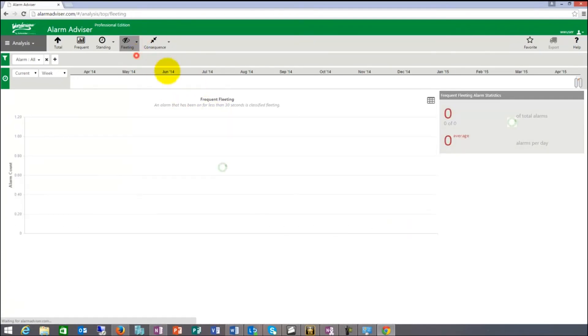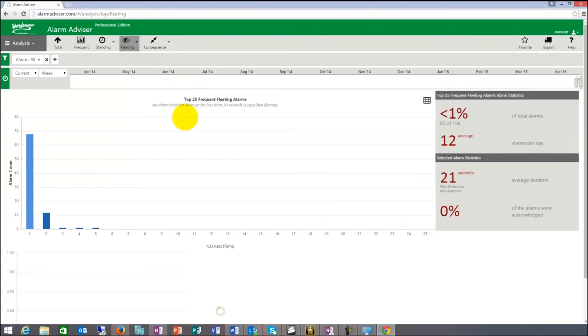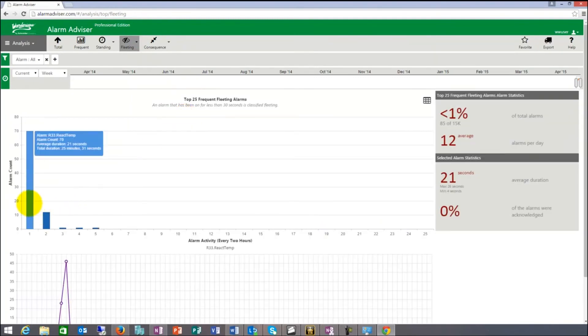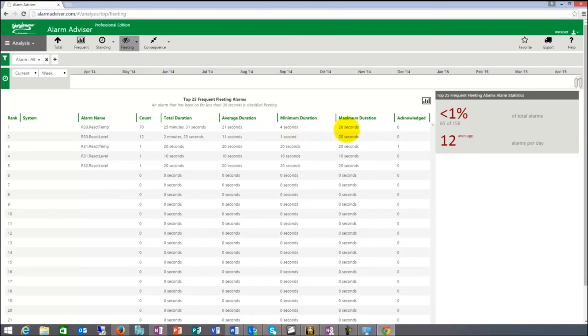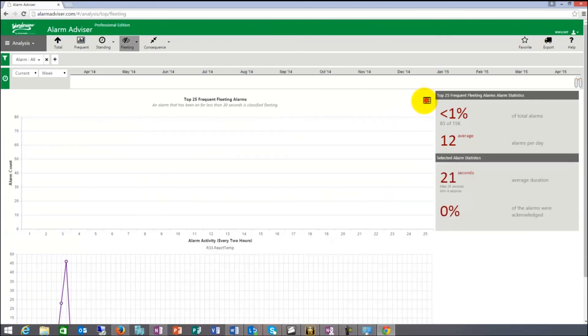There's a total one again and then the most frequent alarms, which in this case is reactor temp. I can switch to list view again and that one has a count of 70. Total duration was 25 minutes. Average duration was 21 seconds. Minimum 4, maximum 26. One time here it was acknowledged. As you can see, that's the fleeting report.